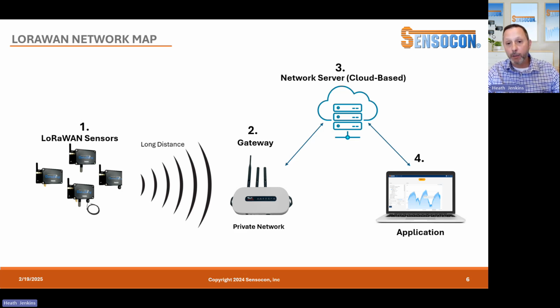Sky's the limit as far as how long you can go. On this platform, you can also set notification thresholds. For example, if the differential pressure in my baghouse exceeds 18 inches of water column, I want an alert, because it's supposed to be pulsed and decrease, and if it's not behaving as it should, that's a problem. There are all sorts of neat notifications you can provide, including low battery, so you don't have to worry about sensors running out without being apprised in advance.